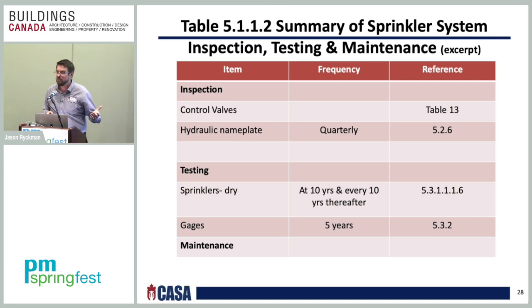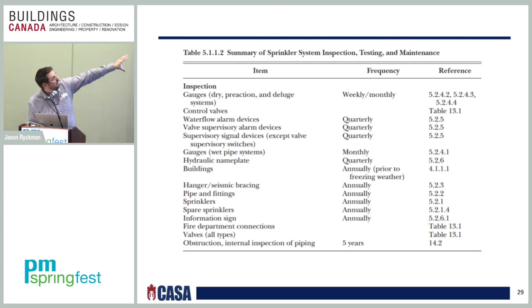Also gauges. If you have gauges on your system, they have to be either tested or replaced every 5 years. So guess what? For most water and air gauges, it's cheaper just to go ahead and buy a new gauge instead of trying to get them all calibrated. And that's 5.3.2. So this basically tells you, in table 5.1.1.2, the summary of your sprinkler system, when you have to do something. And then here's what it actually looks like in the actual standard.